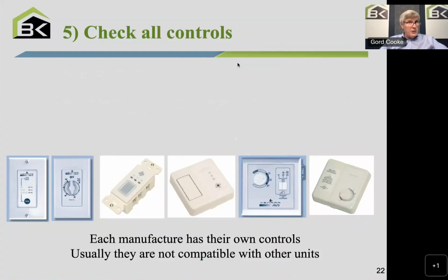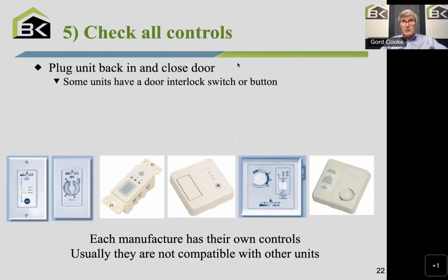And so now we've got the unit clean. We've cleaned the outside grills, we've cleaned the inside, we've cleaned the unit itself. Now we're into thinking about plugging the unit back in and just making sure everything's working correctly. Many units, the unit won't run unless the door is closed. They have a door interlock. So just keep that in mind, so you don't think, you plugged it in, it's still not working. There might be a door interlock.